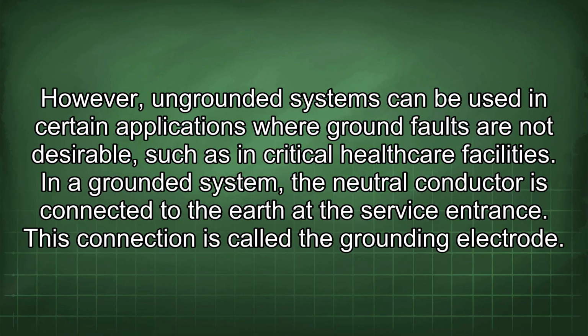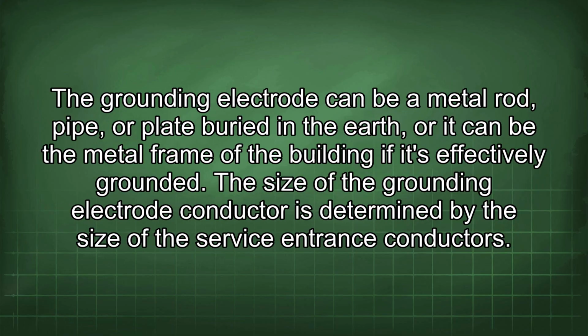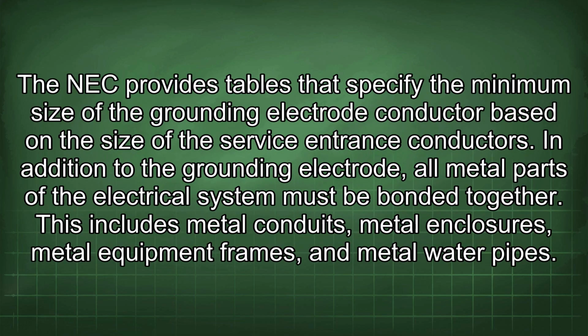This connection is called the grounding electrode. The grounding electrode can be a metal rod, pipe, or plate buried in the earth, or it can be the metal frame of the building if it's effectively grounded. The size of the grounding electrode conductor is determined by the size of the service entrance conductors. The NEC provides tables that specify the minimum size of the grounding electrode conductor based on the size of the service entrance conductors. In addition to the grounding electrode, all metal parts of the electrical system must be bonded together.